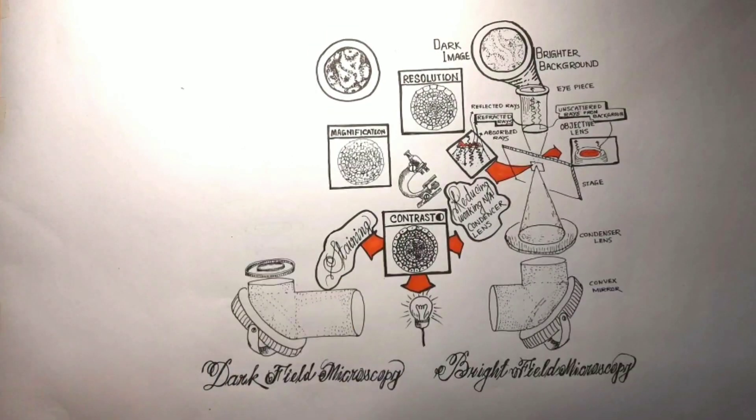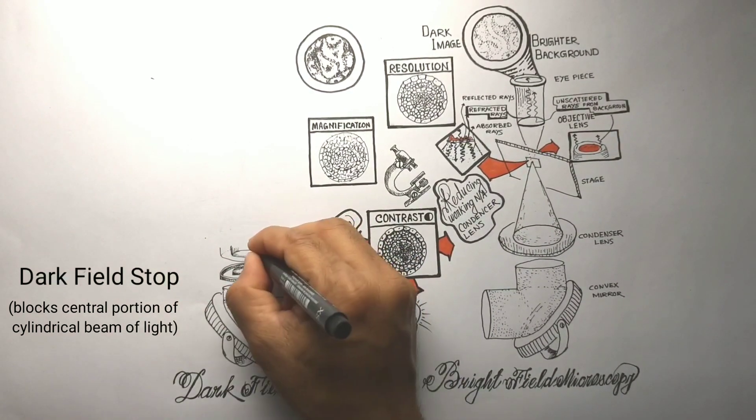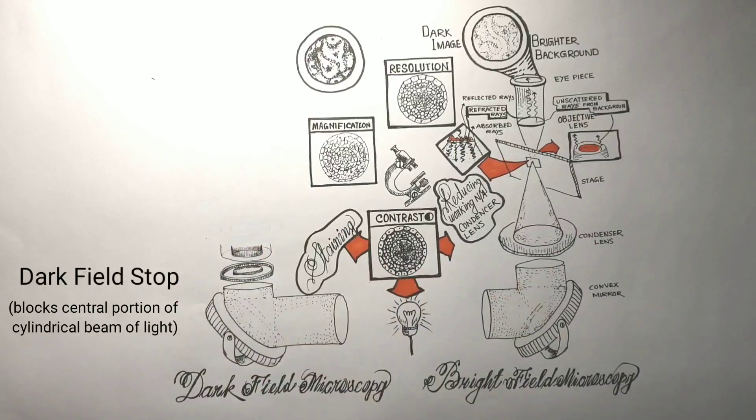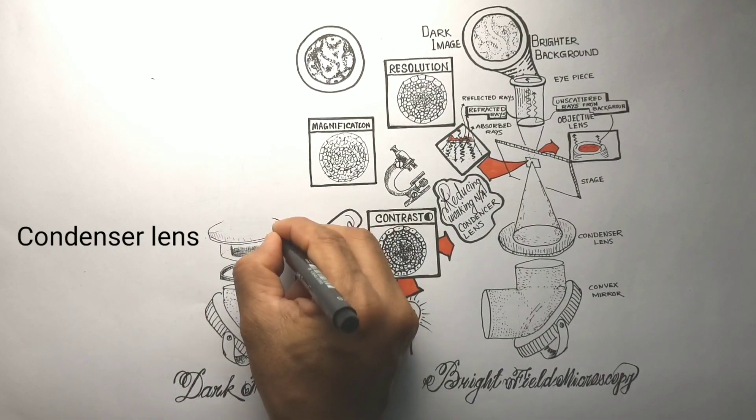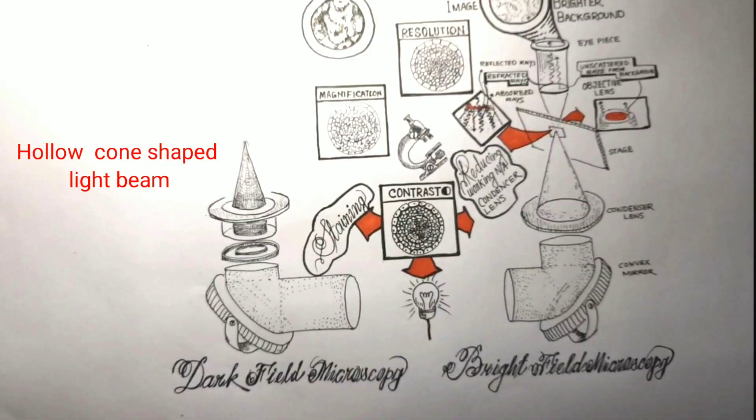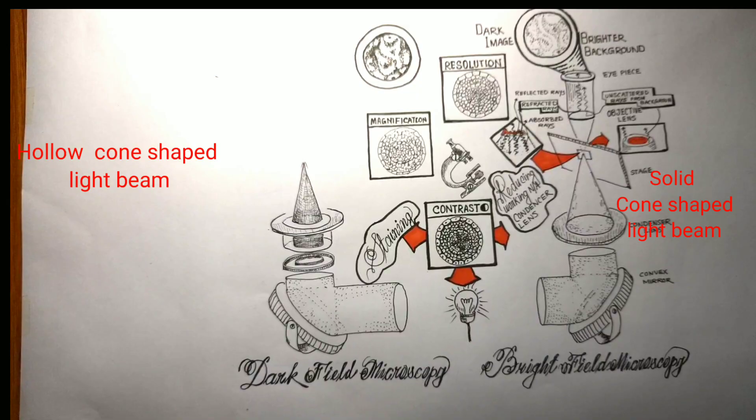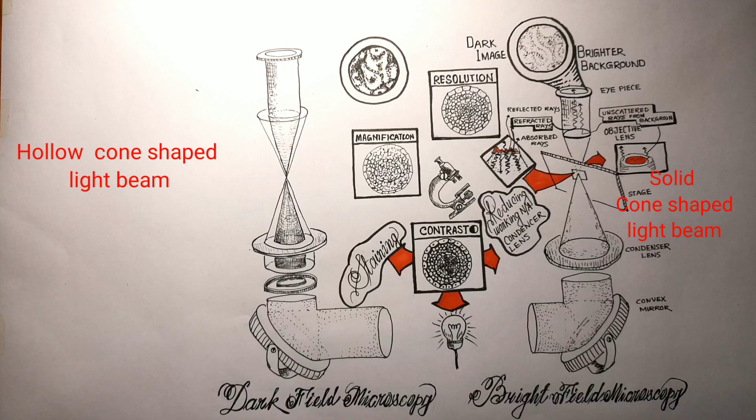In this technique, a disc-like dark field patch stop is used before the condenser lens. The stop blocks the central portion of light from the source and leaves only a hollow cylindrical shape of light beam with a circular layer of illumination. The condenser lens collects this and focuses it onto the sample. Unlike bright field technique where a light-filled solid cone was focused onto the sample, in dark field the condenser focuses a hollow cone of light onto the sample.